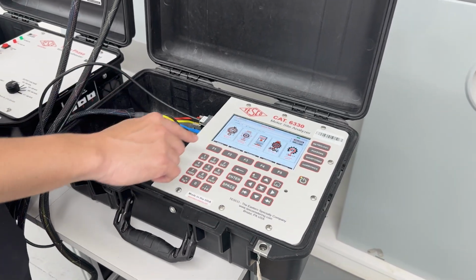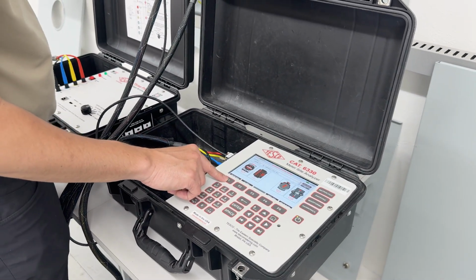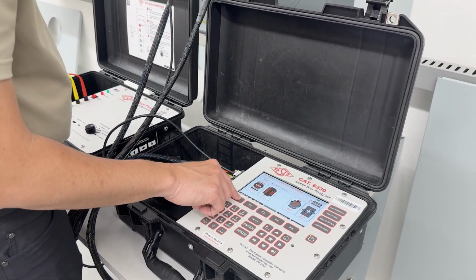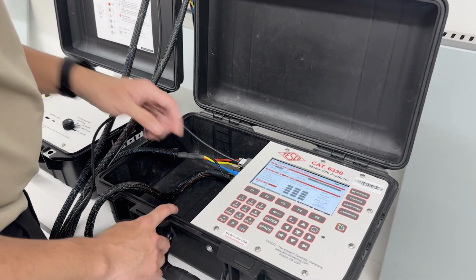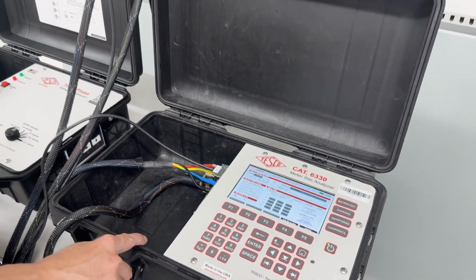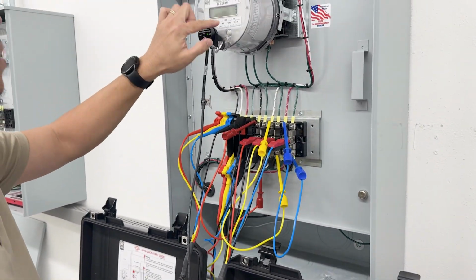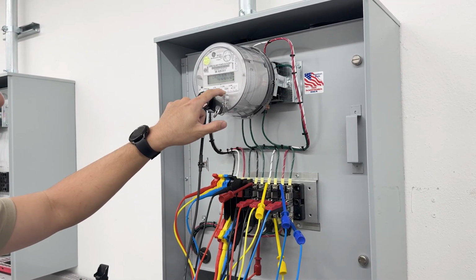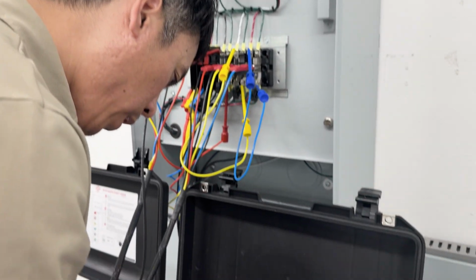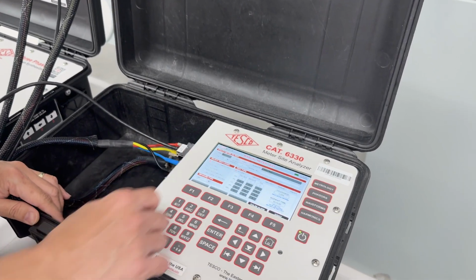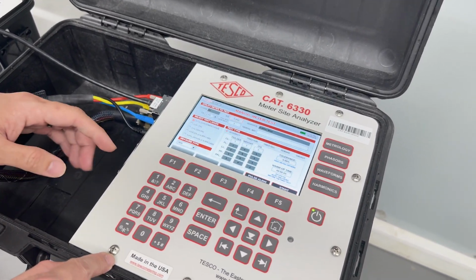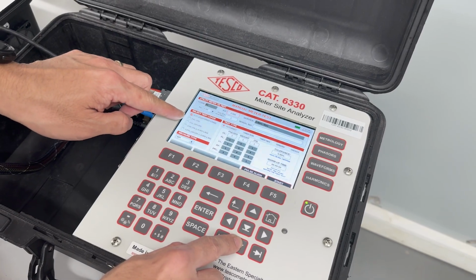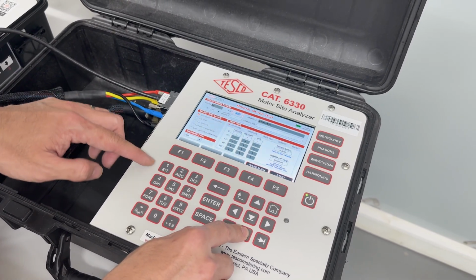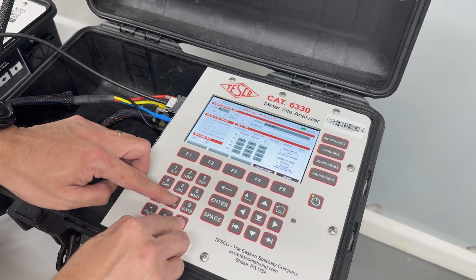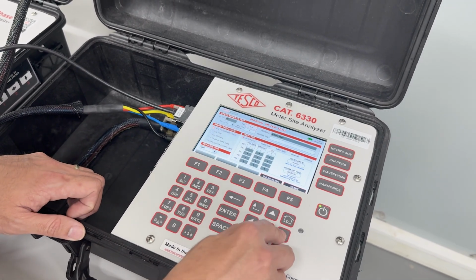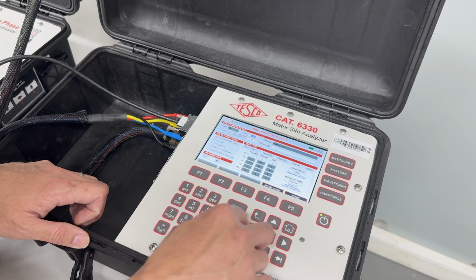So in here, we're gonna run a test. We're gonna run a manual test, and then we're gonna pick a meter test. And in this case, I'm gonna look at the meter. The test amp, I'm looking for the test amperage. In this case, the TA is 2.5 amps. The KH is 1.8. So in here, the TA is 2.5, that's good. The KH is already set to 1.8. And then we're gonna select the test loads, 1.8. I'm gonna click next. How do I do that? 1.8.